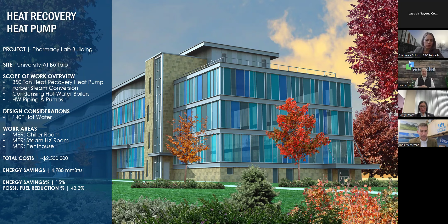As we look further into energy recovery, here's a project example at UB: an energy recovery project at the pharmacy building. Getting a bit technical, but the fundamental idea is this big lab building exhausts 70-75 degree air when it's 0 degrees outside. Why not stop doing that? Instead, take that exhausted energy back into the building and use it to bring in the 0 degree outdoor air needed to ventilate the labs. That's what this project was intended to do.